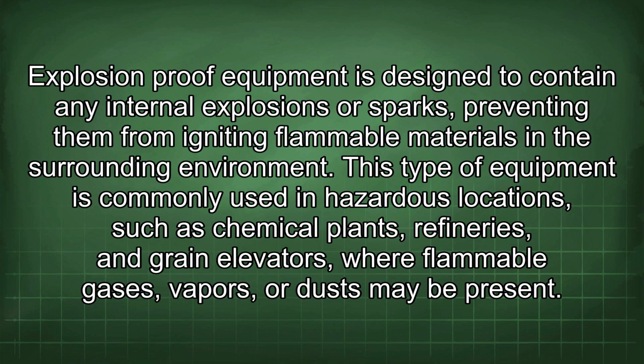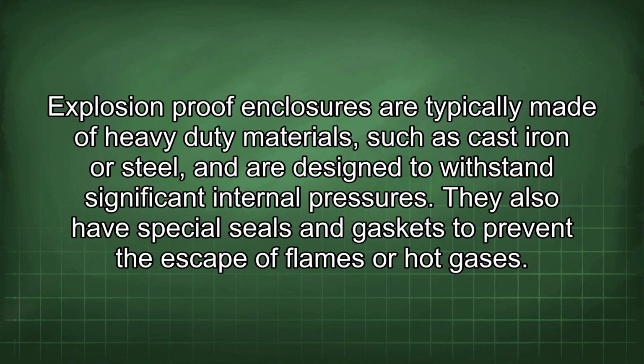Explosion-proof equipment is designed to contain any internal explosions or sparks, preventing them from igniting flammable materials in the surrounding environment. This type of equipment is commonly used in hazardous locations such as chemical plants, refineries, and grain elevators, where flammable gases, vapors, or dust may be present. Explosion-proof enclosures are typically made of heavy-duty materials such as cast iron or steel, and are designed to withstand significant internal pressures.